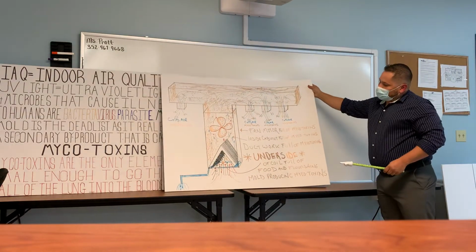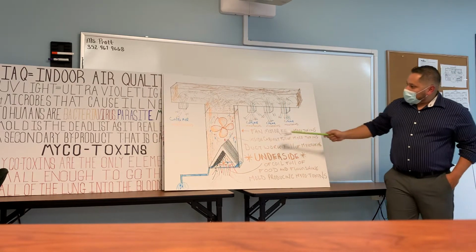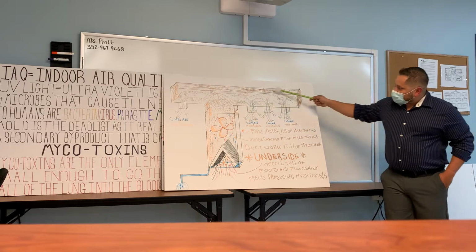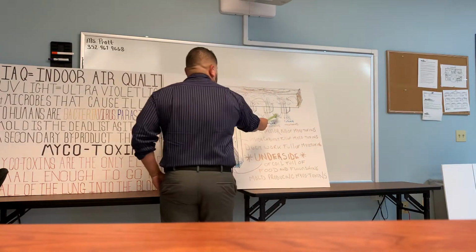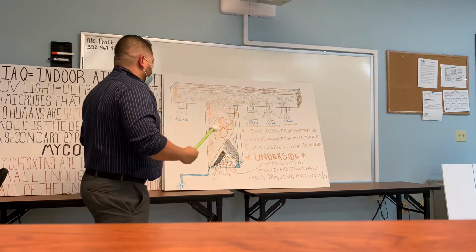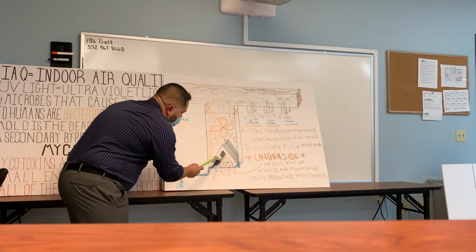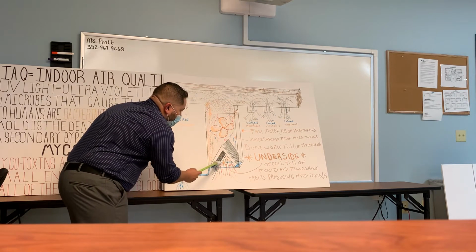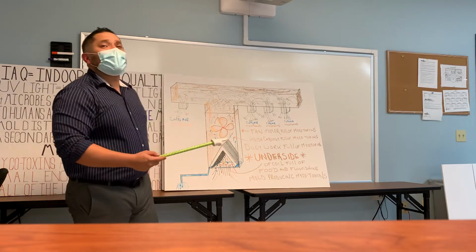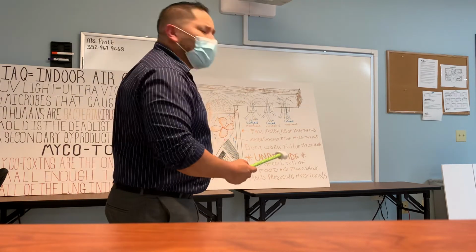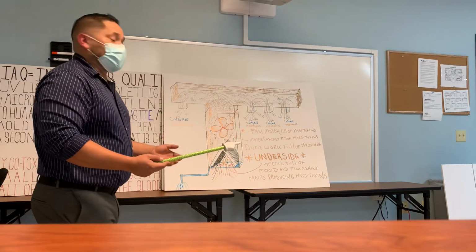Now, what we can see is this is the same system. We have now mycotoxins that have infested the fiberboard ductboard. There's cold air coming out because you turned it back on, you changed the capacitor, but there's also mycotoxins mixed with it. When you look underneath the coil, you'll see now that it's black, it's covered with food. This is the mold that's been living because it's been running maybe 3-5 years without a filter. Very common, especially in rental units. Most folks just don't know what the filter's for.